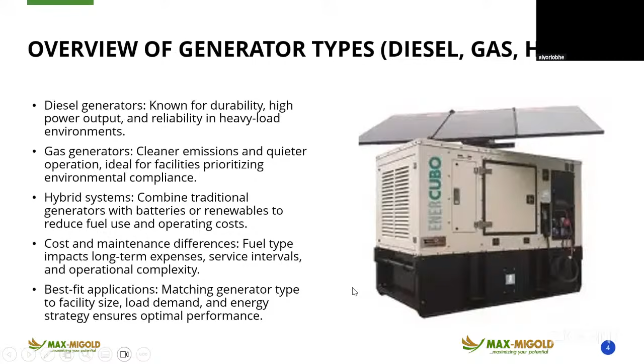Like I was saying, we stop at the hybrid type of generator. We have the hybrid one, the gas one, and the diesel type. The best practice is to ensure you have a good load analysis to size the type of generator for your facility. You don't just buy a generator because you want to. The load must be determined, and what can best power your facility is also key. So after determining the load, the wattage, everything, you need to recommend the correct size of generator for your organization or facility. You don't just recommend a generator; load analysis must be carried out by experts for a generator to work effectively.